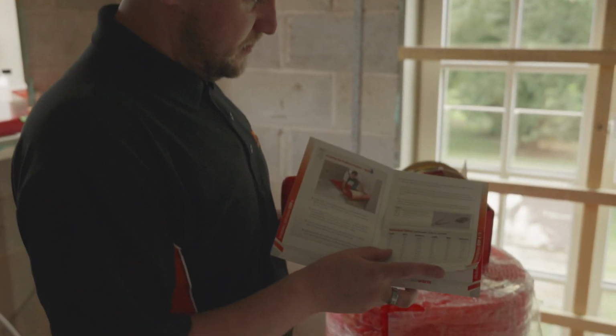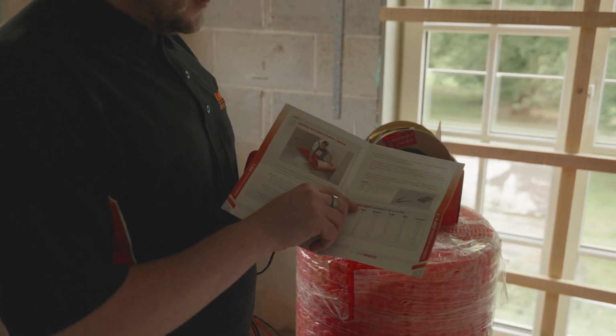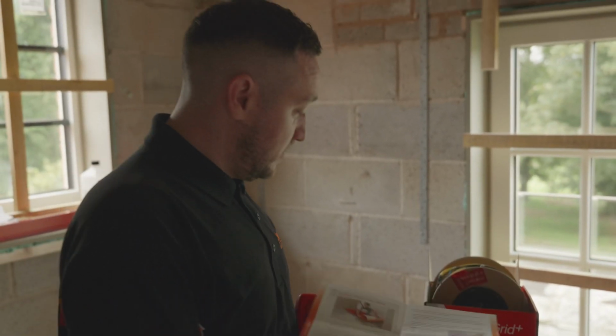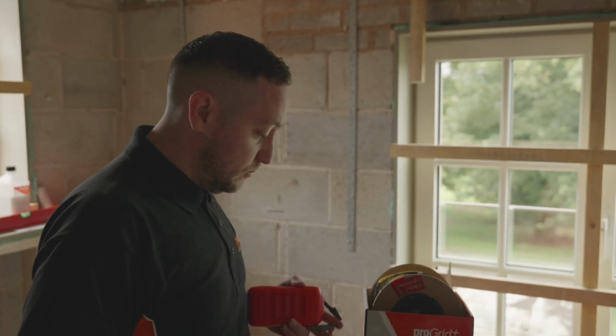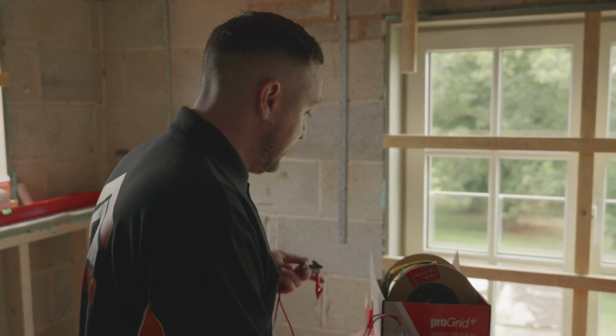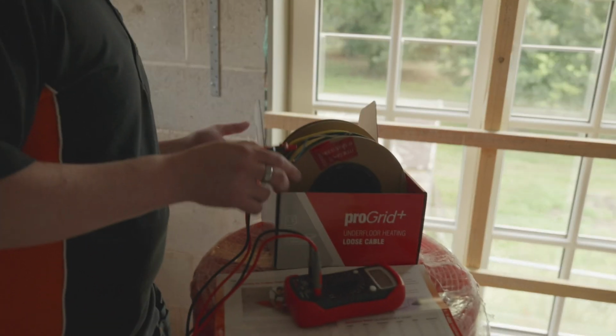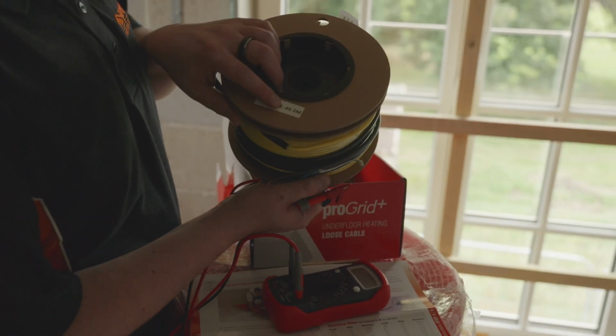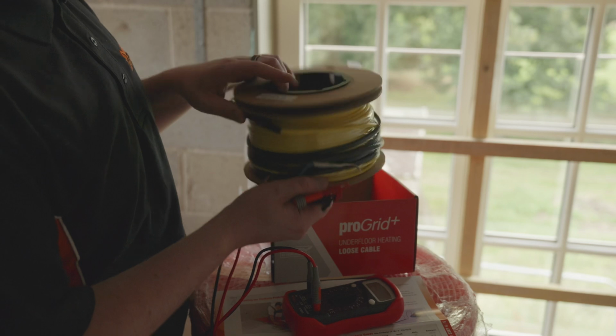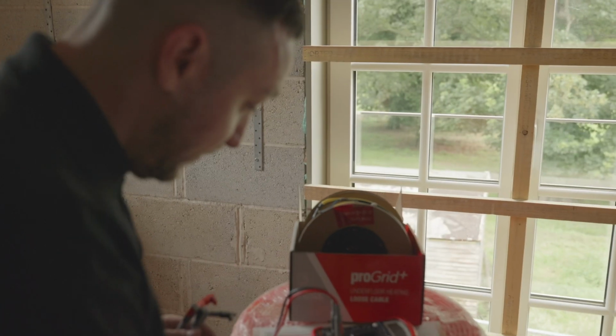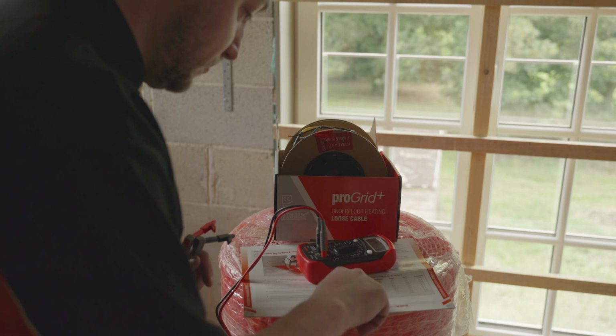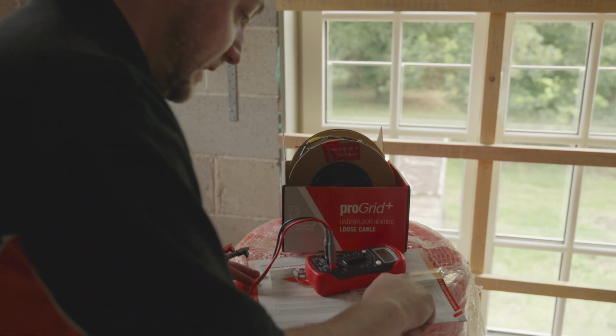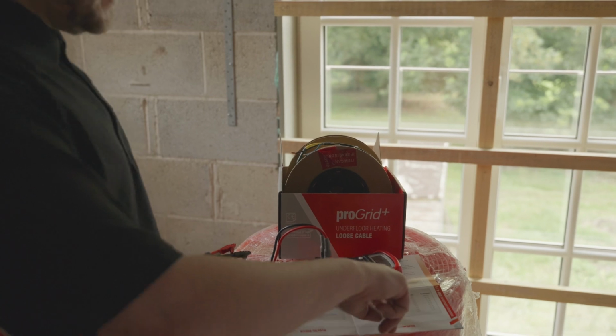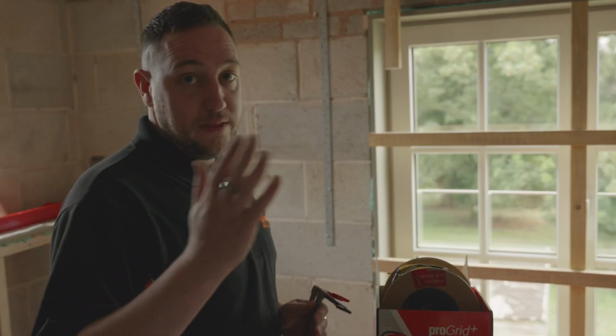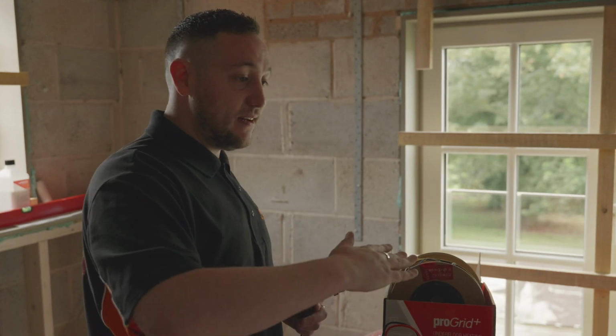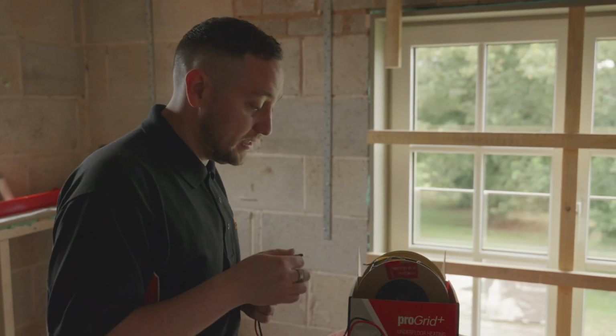Find the section where it says resistance values. This tells us what the resistance of the cable we're installing should be. In this instance, we've got a 49.3 linear meter length. If we find that in our table, 49.3 meters should measure at 78.37 ohms, or to within 10% of that value. So anything from 71 to 85 is still a pass on that test.